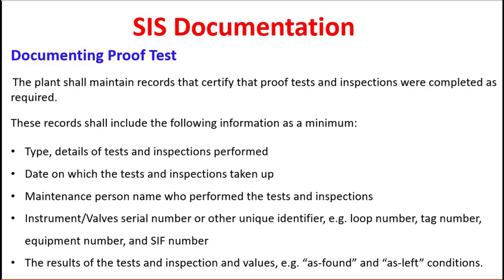These records shall include the following information as a minimum: the type and details of tests and inspections performed; the date on which the tests and inspections were carried out; the name of the person who performed the tests and inspections; and instrument or valve serial numbers or other unique identifiers — for example, loop number, tag number, equipment number, and safety instrumented function number. These requirements may vary according to the geographical location of the company, governmental regulations, and the company's own management directives.